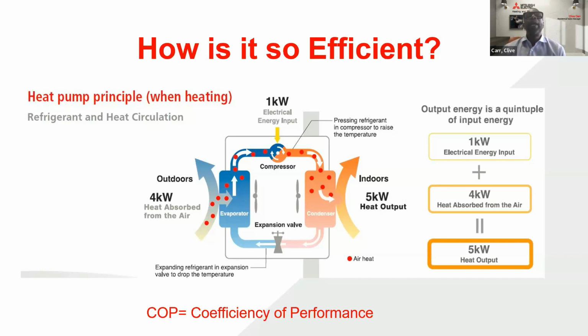So now you end up with a ratio of 4 to 1, and this is where your efficiency comes in, where for every 1 kilowatt hour of electricity that you're purchasing, you're getting approximately 5 kilowatts of heat. So you can see the benefits there, right? I buy 1 kilowatt of power, but I'm able to deliver 4 to 5 kilowatts of power and heat. So it makes using 1 kilowatt of power very efficient. Instead of paying for 5 kilowatts of heat, I'm only paying for 1 kilowatt. And this is how you get the efficiency from the air source heat pump, making it the most energy efficient equipment on the market for heating your home.